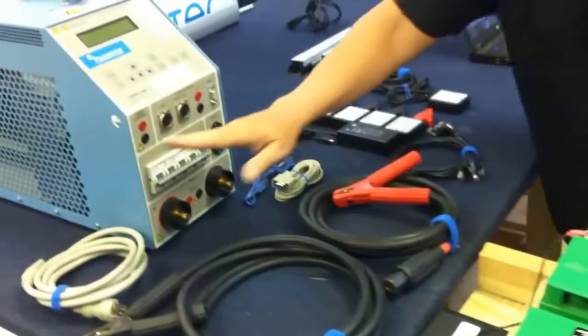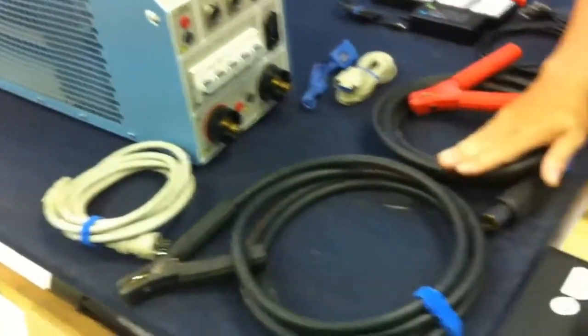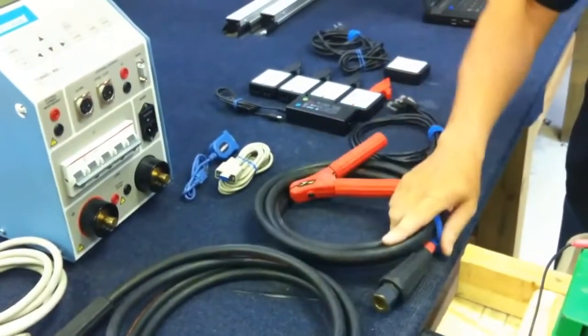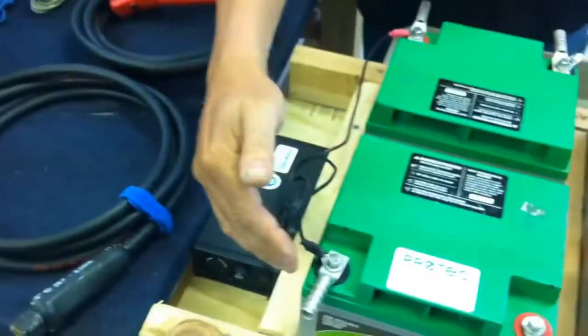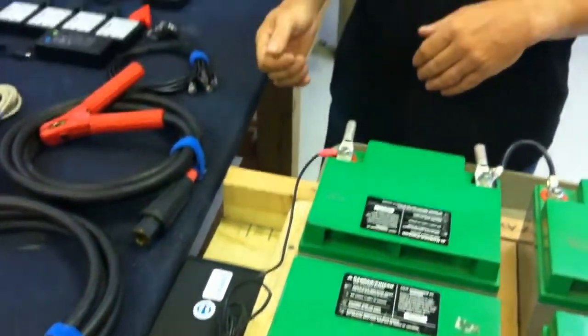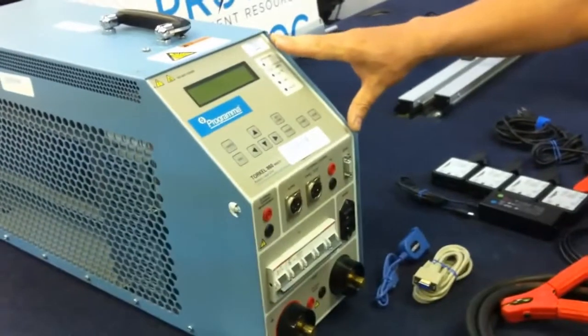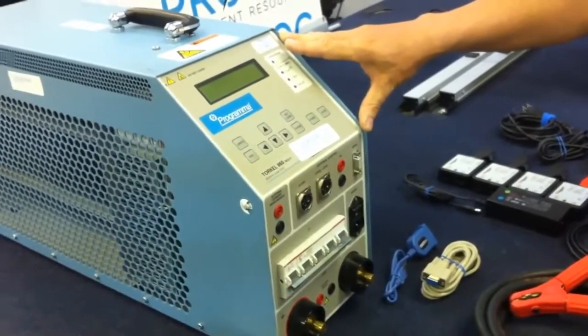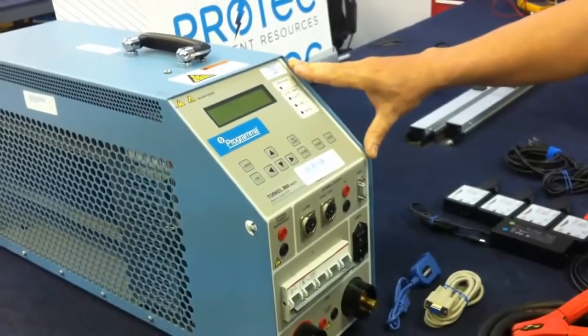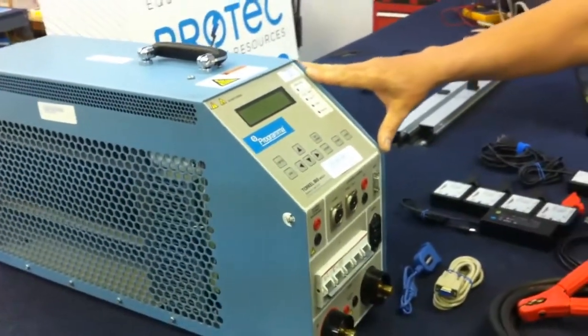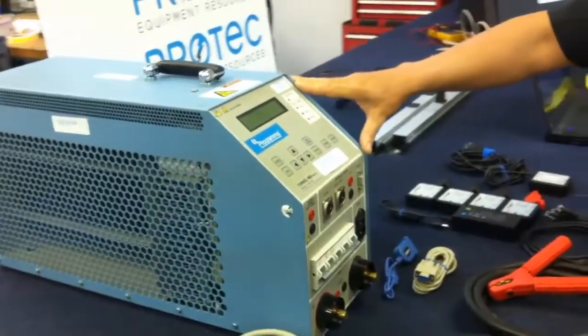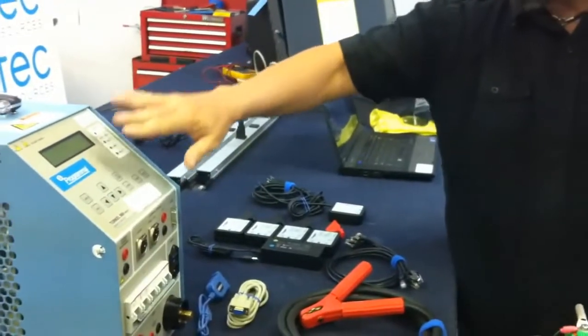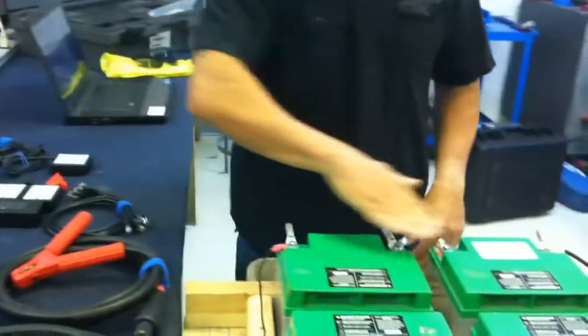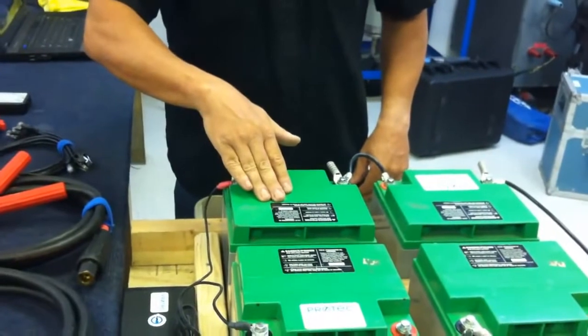Some of the accessories that come with the instrument: we have the power cord, and your test leads, which get connected onto the terminals of the battery bank that we're going to be discharging. The TORKEL itself will actually regulate and control the rate of current discharge. You are capable of doing what they call constant current discharge through the TORKEL. It will monitor the entire voltage of the entire battery string.